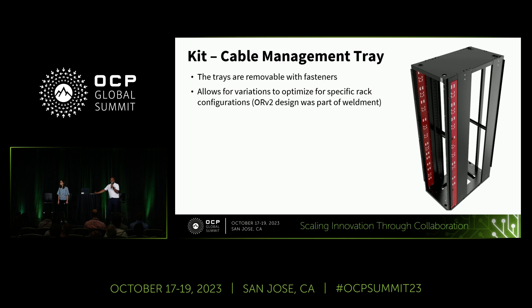In this slide, I'll quickly go through cable management. On V2, cable management is part of the vertical, welded to the frame. In V3 development, we made the cable manager an assembled component. In a data center situation, if you want to pass cables from one rack to another — even with a door fitted — you can do that by removing the cable manager. The community can also change the features or cutouts of the cable manager, which can be designed and replaced.